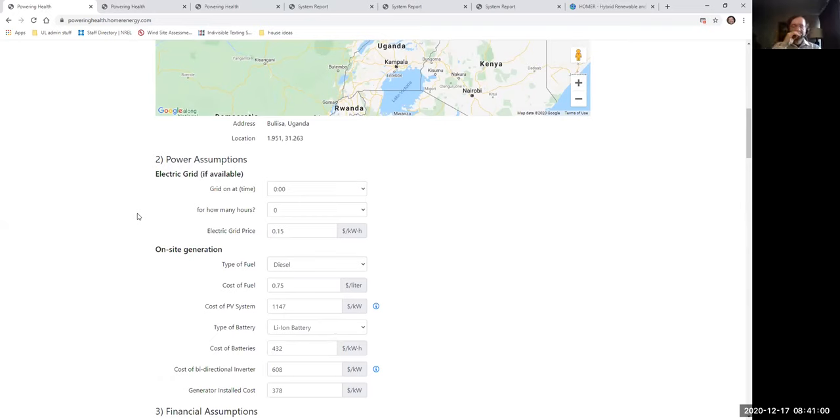You can put a constraint on the design that says, design a microgrid that emits no more than X amount of carbon. You can do a sensitivity on that number and create a graph I find very interesting that shows that the least cost system produces a lot less emissions than a pure diesel system. By adding more and more PV and batteries, you can reduce the emissions even further. It gets very nonlinear as you try to go to zero. And that's a really useful graph to look at. You can do the same thing with any of the other emissions, like nitrous oxides, sulfur, particulates, and volatiles. Most of the interest is in carbon, but you can do it for any of them.